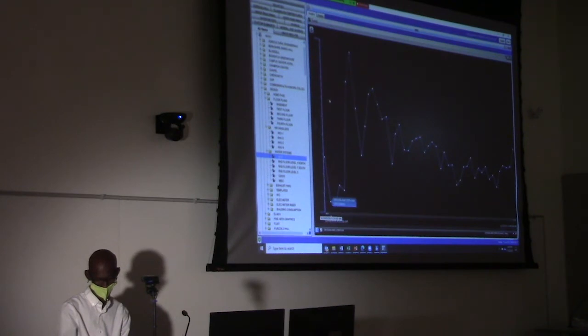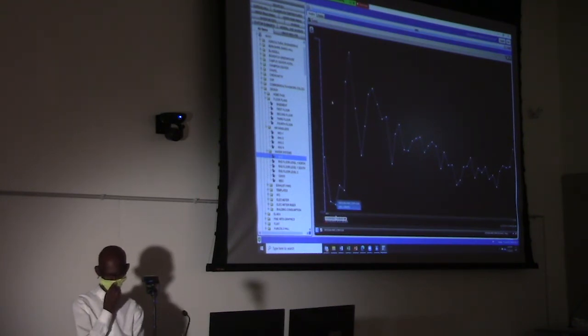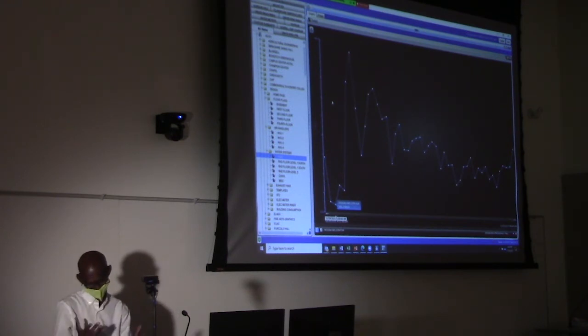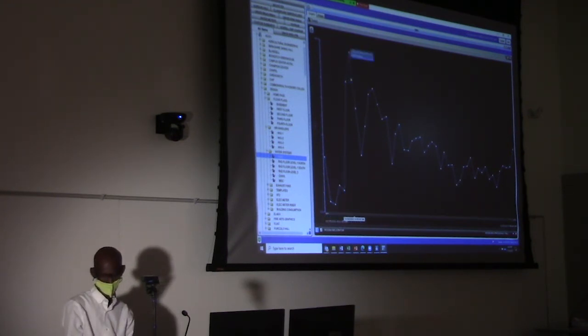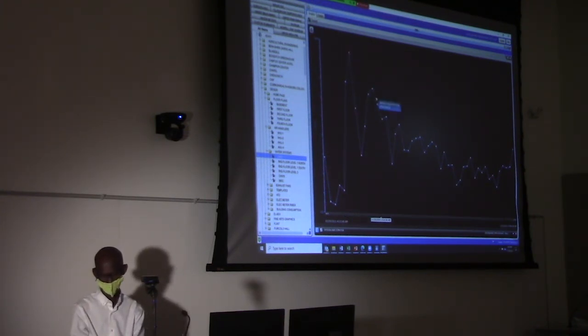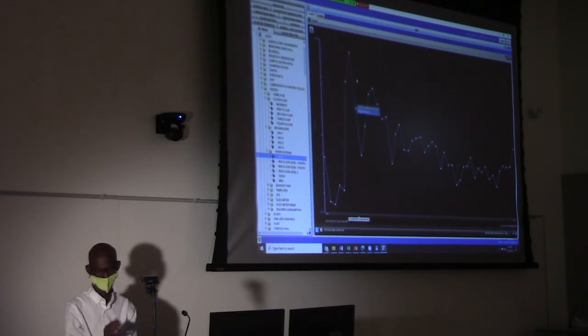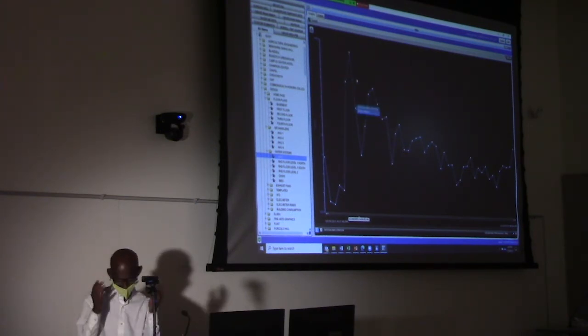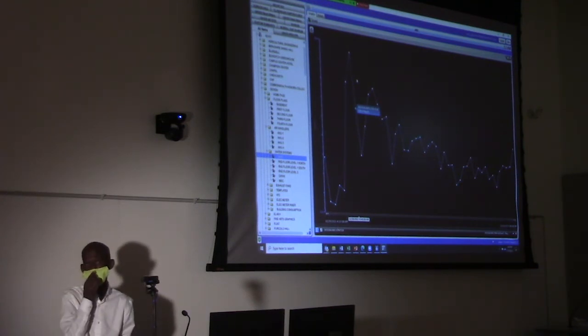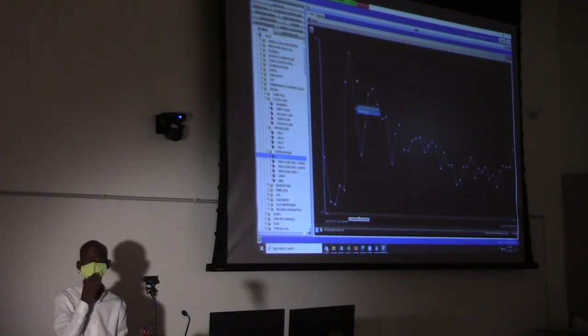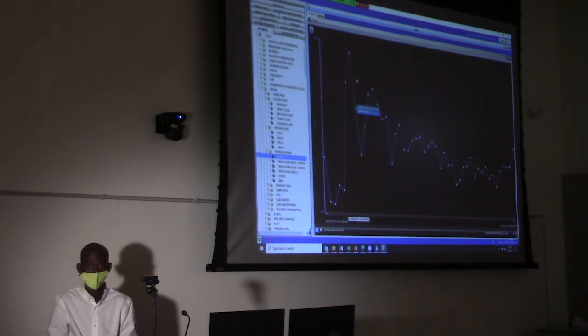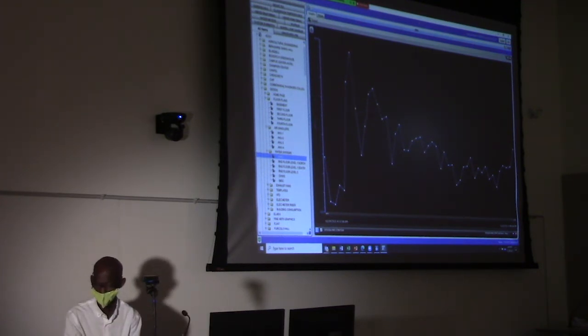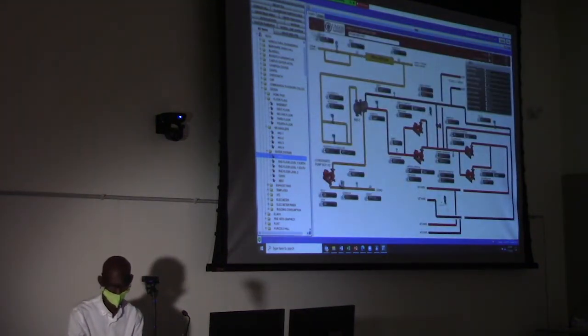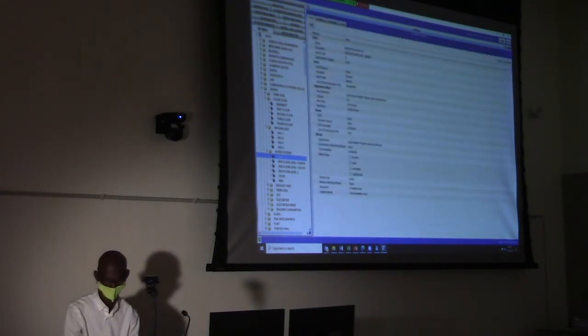For the last 12 hours, you can see it was using 160 pounds of steam. And all of a sudden it went to 840, that was at 6:30. And then it went down, and it's been going down. The reason it went up, probably, we look at the trend there, may be because we don't start the IMM unit till 6 in the morning. So, that's one picture.